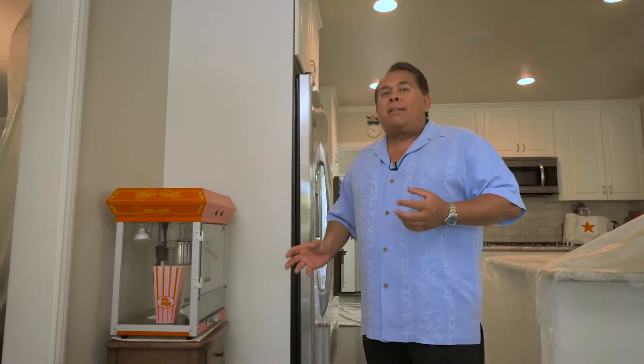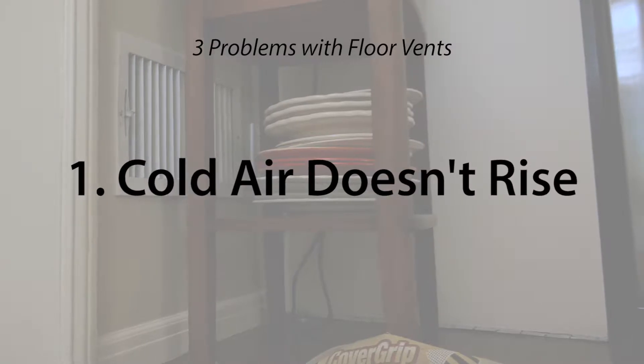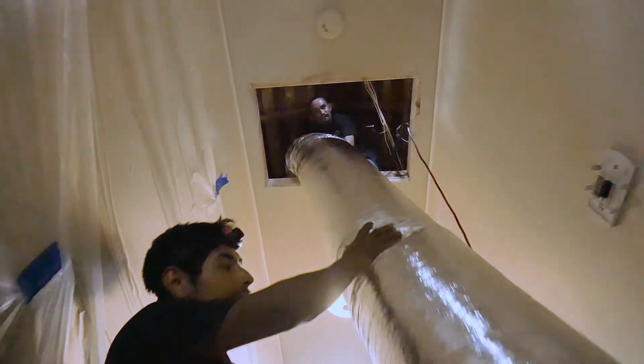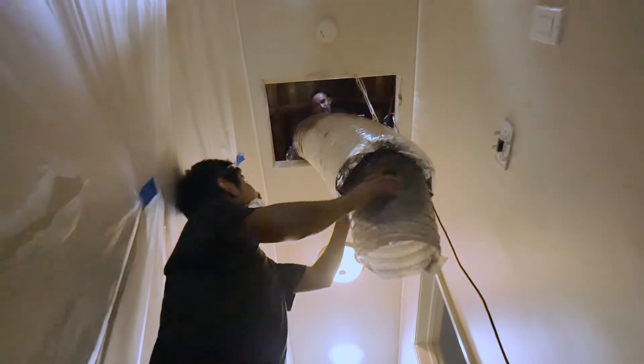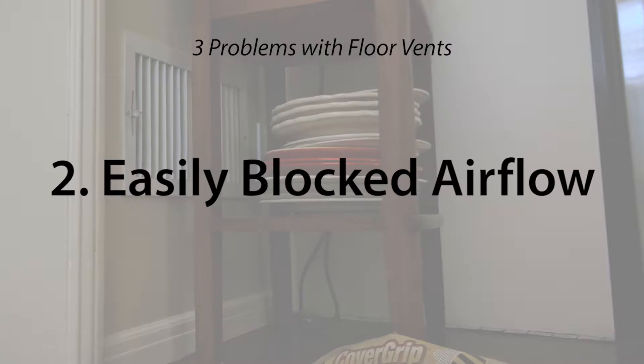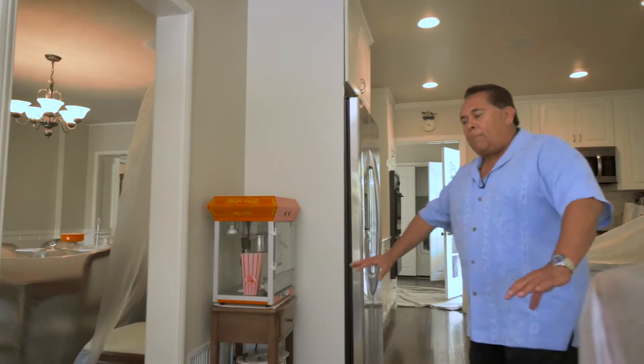The problem with our business is that cold air doesn't rise. When a lot of these houses got retrofitted with air conditioning 20-30 years ago, they simply reconnected to the old floor vents. As people furnish their homes they block those vents, so the best they get is cold air curling across the floor, keeping only that low area cool.